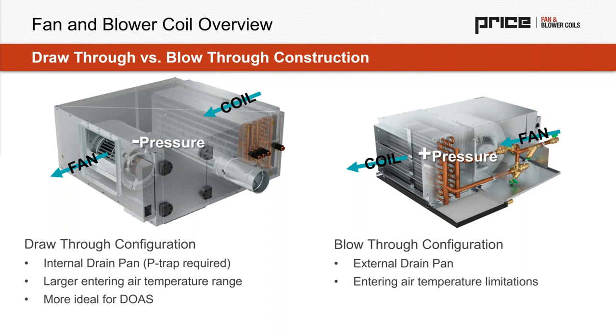Other differences: a draw-through product, if we look at a makeup air application, is possible because we're able to condition the air before it actually interacts with the motor, which has more temperature limitations. So we see a larger entering air temperature range for a draw-through product. And I would also argue, especially when we look at DOAS applications, draw-through products are a little bit more ideal. And I want to look at why that's the case.